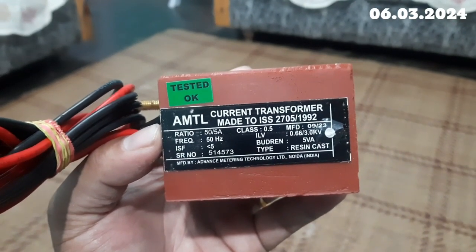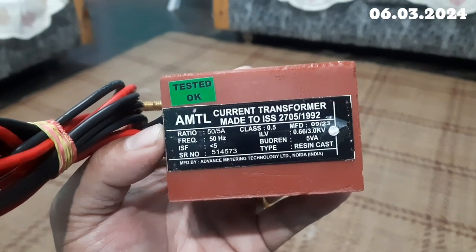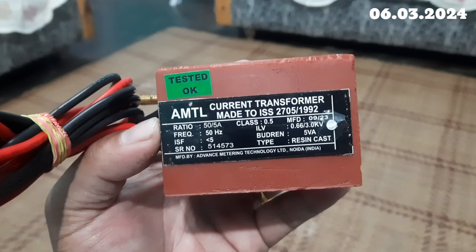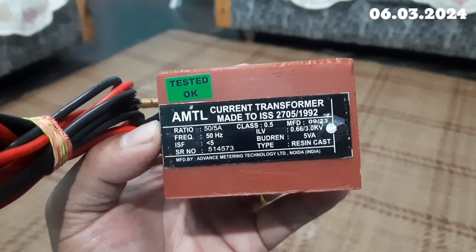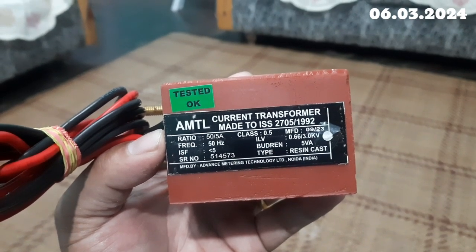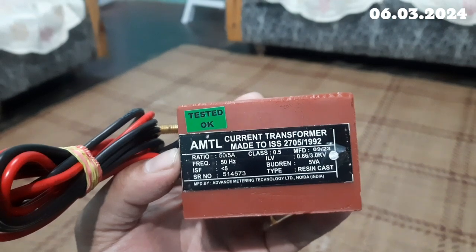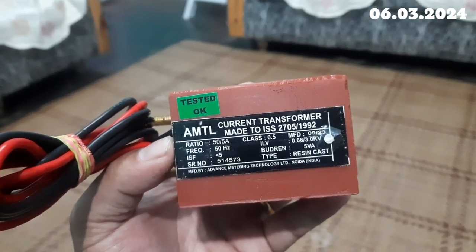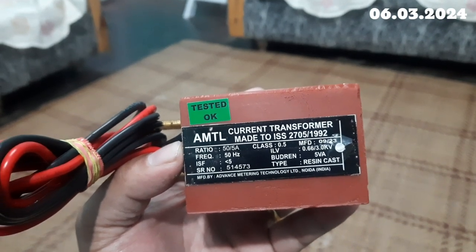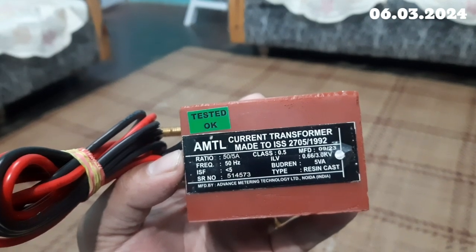For example, if the fault current is 5000 ampere and your rated current is 1000 ampere, in case you take a CT ratio of 1000 by 1, then in that case your ISF value is 5. It should not be more than 5, because if it's more than 5, the CT core will get saturated, and the secondary current will be 0, and you will not be getting the readings.